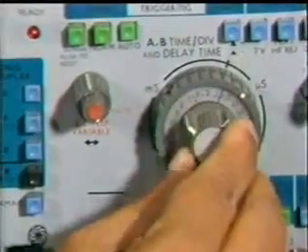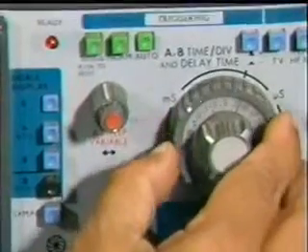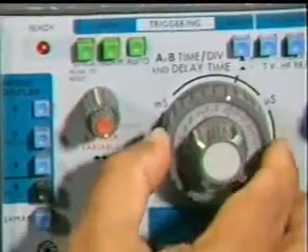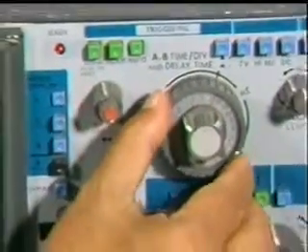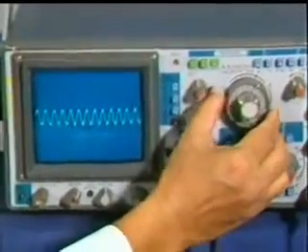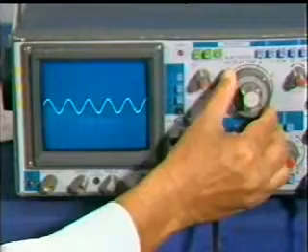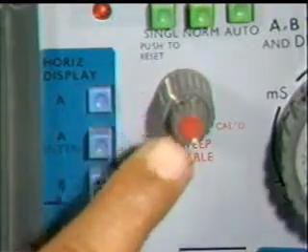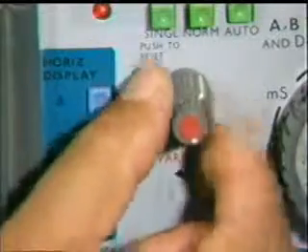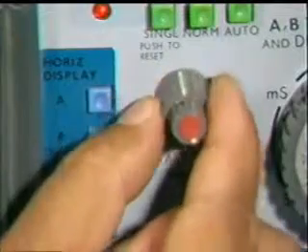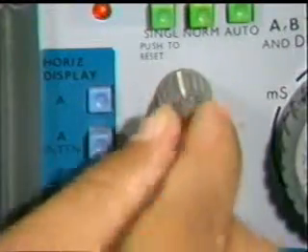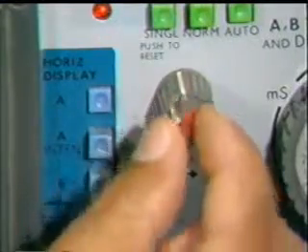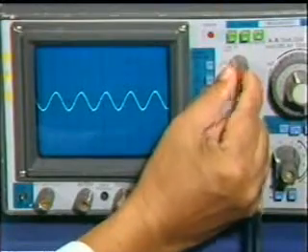The smaller knob is for delay time division. You can bring the required number of cycles of a given signal on the CRO screen with this knob. The lower portion of this dual knob is for horizontal positioning, and the upper one is for sweep variable. By this upper knob, the number of cycles can be varied between the locked and unlocked position.